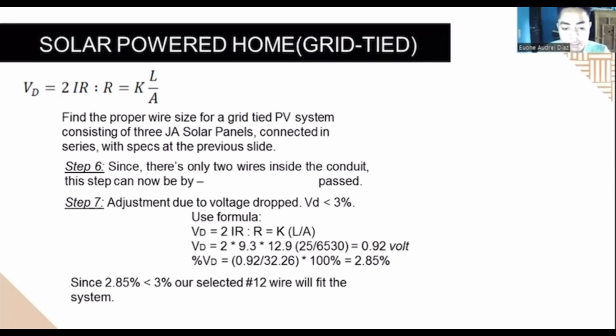Voltage drop is the amount of voltage loss that occurs through all or parts of the circuit due to conductors. The voltage drop is equal to 2IR, and R is equal to K multiplied by L over A. VD is equal to 2 multiplied by 9.3 multiplied by 12.9 multiplied by 25 over 6,530, which is equal to 0.92 volts. Percent VD is equal to 0.92 over 32.26 multiplied by 100%, which is equal to 2.85%. Since 2.85% is less than 3%, our selected number 12 wire will fit the system.